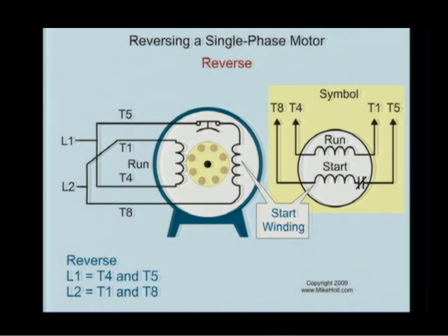The drum switch. So the way the drum switch is working: when I go in one direction, I'm taking line 1 to the start winding, and then I'm taking line 2 to the other, connecting them in parallel. On each of the windings I'm just connecting line 1, line 2. And then when I move the drum switch in the other direction, I'm still maintaining line 1 and line 2 on the run winding. I'm just changing the polarity of the start winding through the drum switch. And then bingo, it goes back.